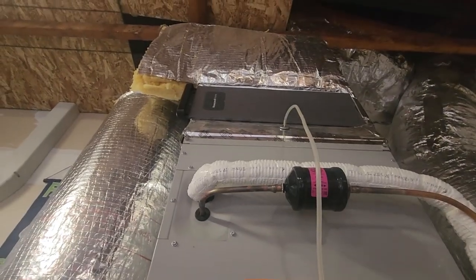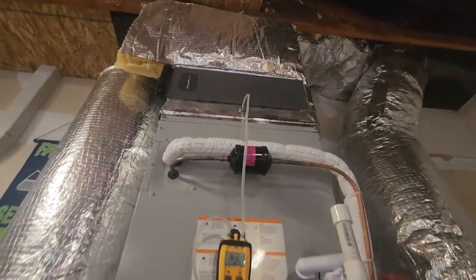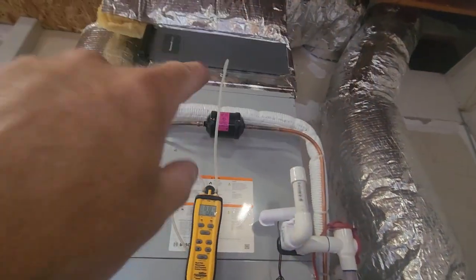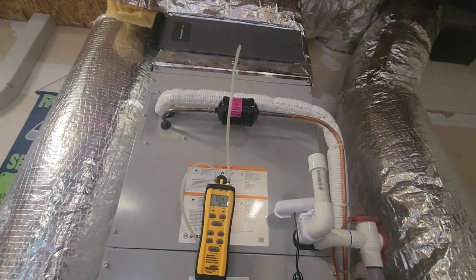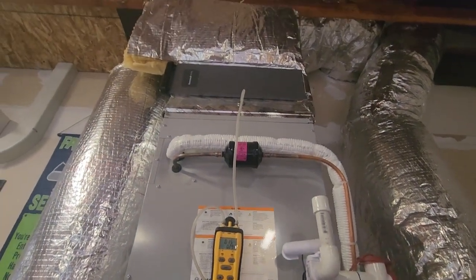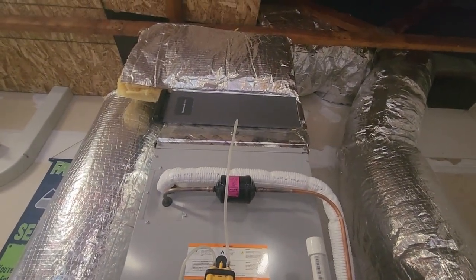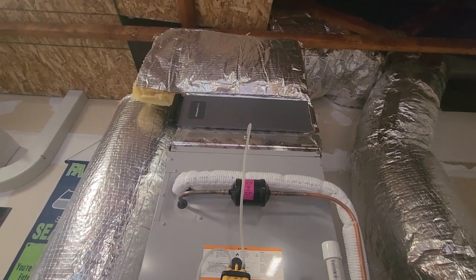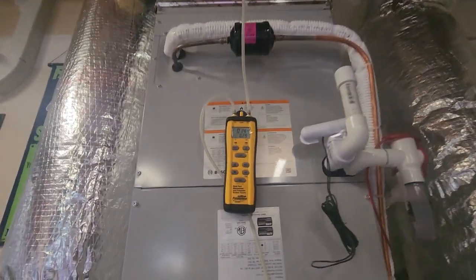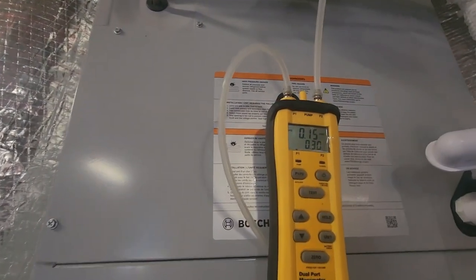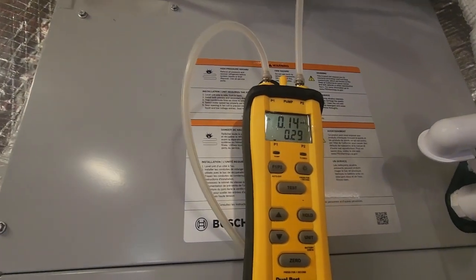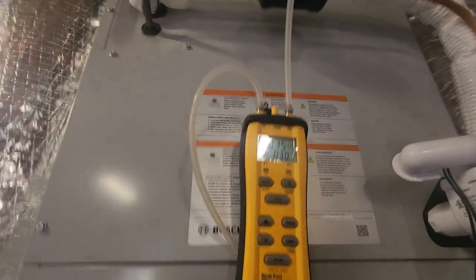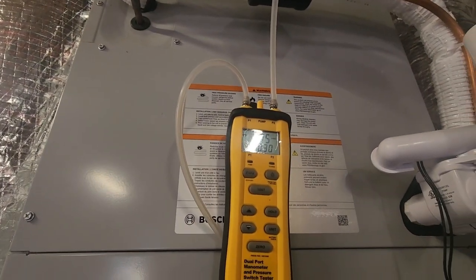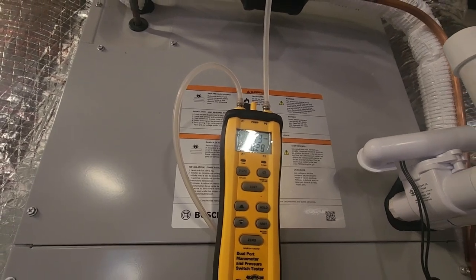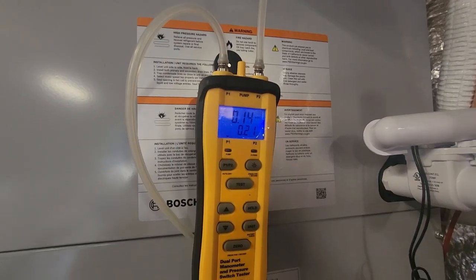So those filters are awesome. That's my entire duct, my entire return run with my filters, 0.14. That's awesome. That's why it's so important to keep your filters clean, guys. It'll keep your equipment running a lot longer, and it'll keep it running more efficiently for sure. So let's pull that filter out and see what we got, and we'll do the same thing. We'll do each zone, and then we'll do both wide open and see what we got.